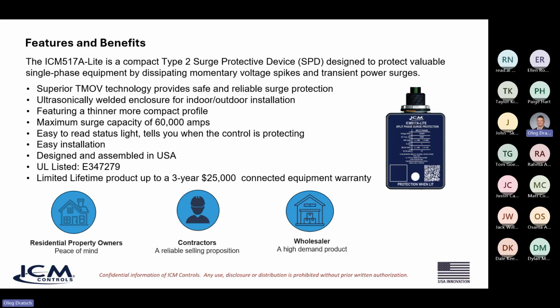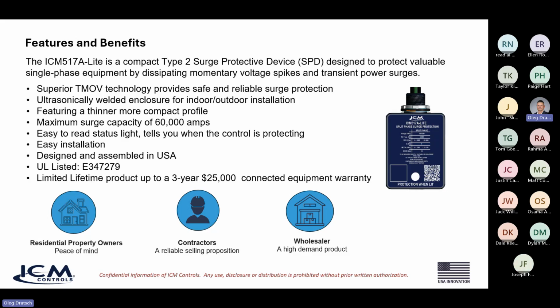If we talk about the features and benefits of the device, like I mentioned, TMOV technology. Some other companies are using different technologies. They may be using substandard TMOV components. But we really do a good job sourcing these components, and so they provide safe and reliable surge protection. The device itself is ultrasonically welded, so that means it can be used outdoors. It's NEMA 4X rated. And it's not that big. It's definitely smaller than a phone. It's probably 2 inches wide by 3 inches tall. So really it'll fit into any knockout or inside of a compressor anywhere you want to install it where there's a knockout.